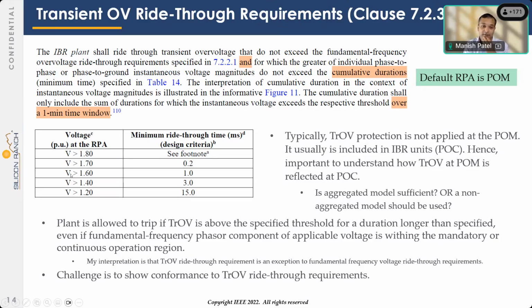Again, this is a cumulative time over a 1 minute time window. These times are in milliseconds. So 15 milliseconds is less than one cycle, right? And this is cumulative over a 1 minute window, so a lot more cycles. So how would you even measure that in the real world? So anyhow, I think the intent of the requirement is clear.